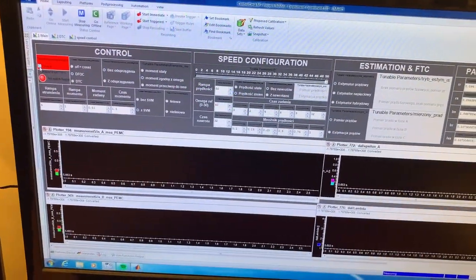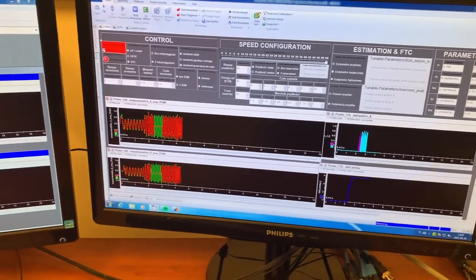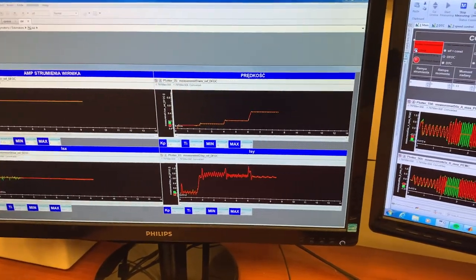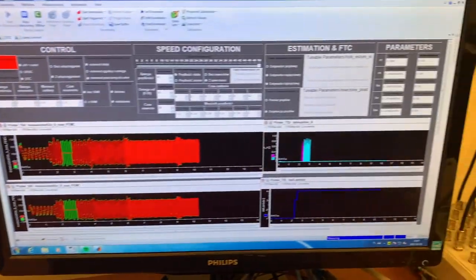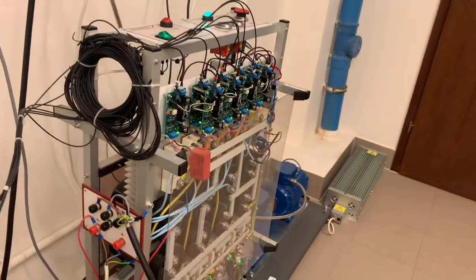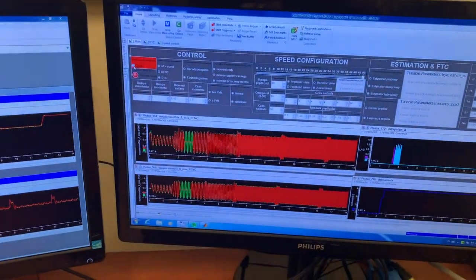In the presented work a stator current estimator called virtual current sensor has been proposed, which allows fault detection of a faulty sensor and a smooth transition to the control in emergency mode. In case of the outage of both current sensors in the drive it enables the current sensorless mode operation.